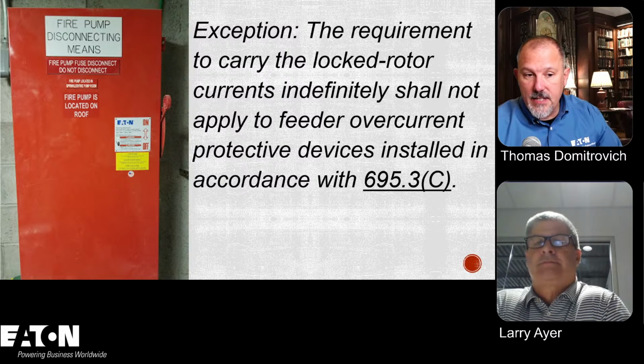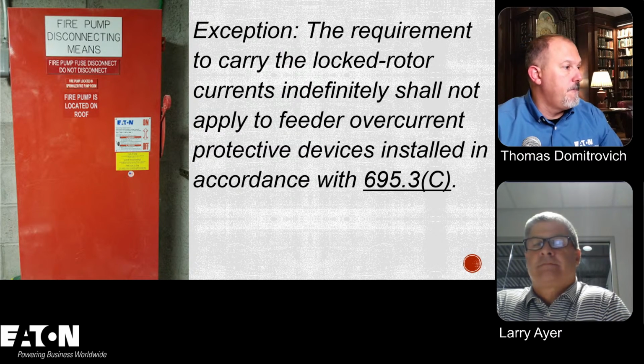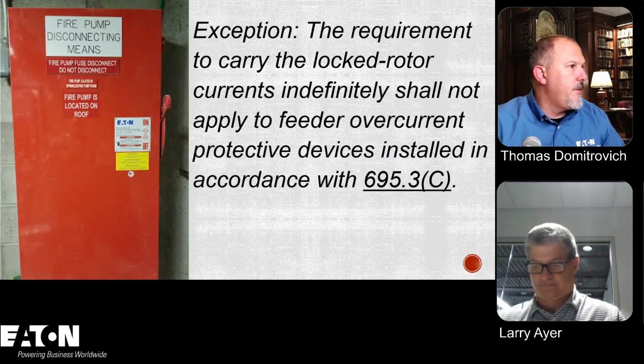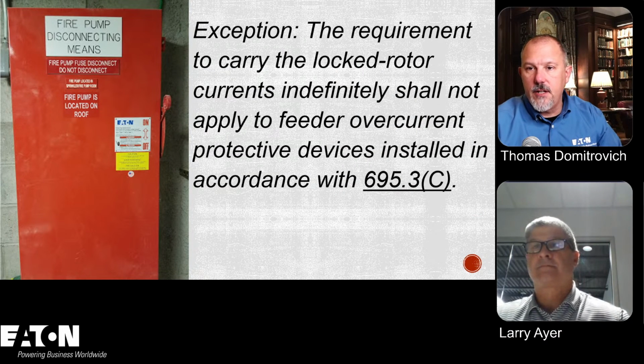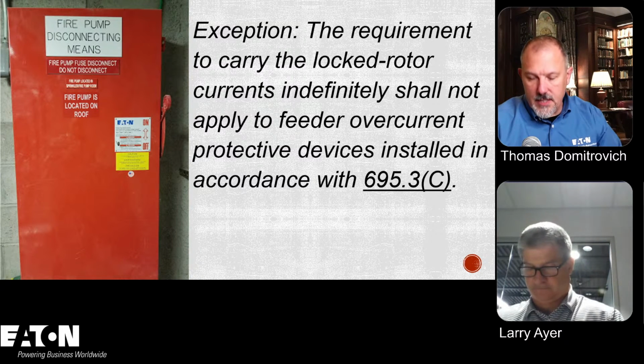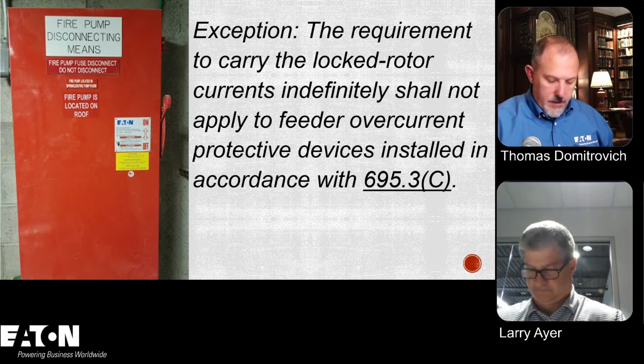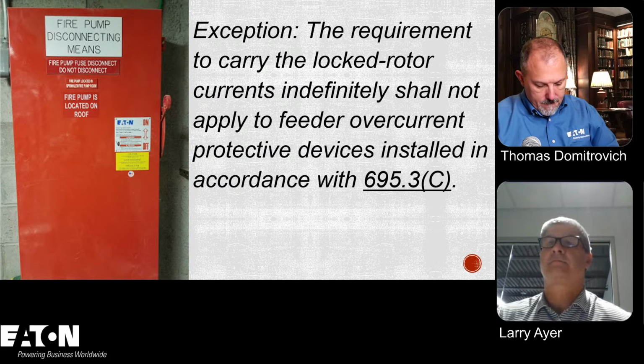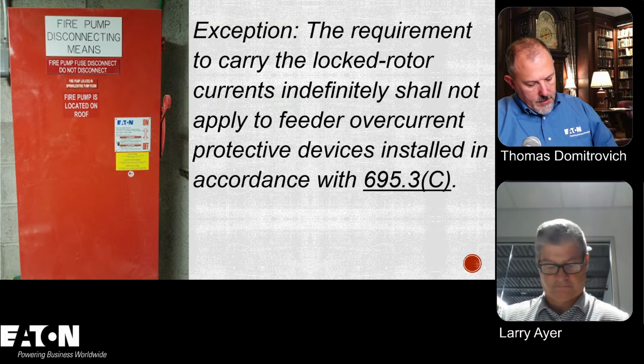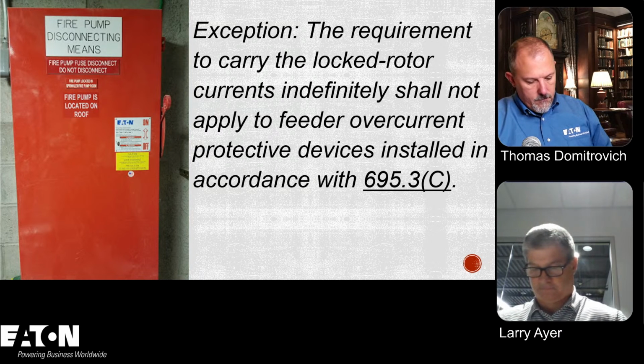Transformer must put out 600% full load amps at allowed rated voltage drop. We're going to get into the voltage drop concerns and whatnot. So when you have that transformer, those are some important details when you're picking the transformer and sizing your overcurrent protected device. Correct. Did we hit this one? Exception: the requirement to carry locked rotor currents indefinitely shall not apply to feeder overcurrent protected devices installed in accordance with 695.3(C). And what is 695.3(C)? And that's your multi-building? Is that what that is? Yep, that's your multi-building campus-style complex.